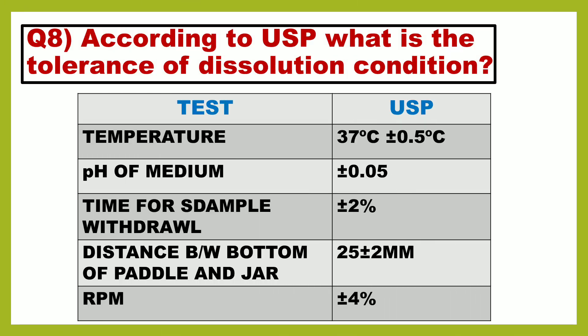Next question is: according to USP, what is the tolerance of dissolution conditions? Temperature: 37°C ± 0.5°C. pH of the medium: ± 0.05. Time for sample withdrawal: ± 2%. Distance between bottom of paddle and jar: 25 ± 2 mm. And RPM: ± 4%.